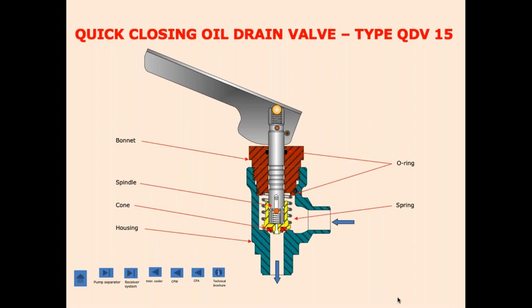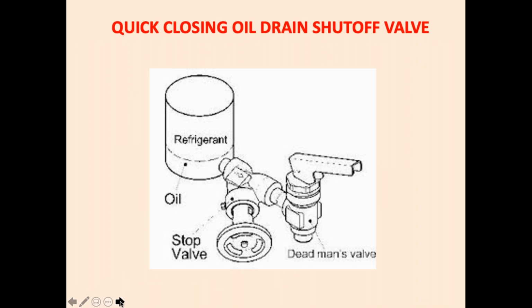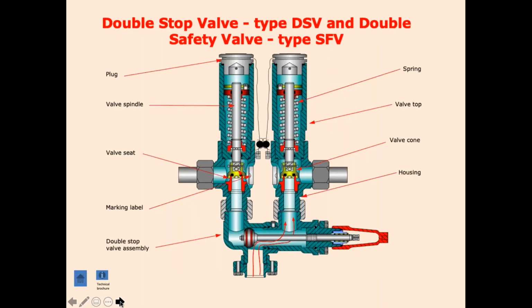It has a stop valve also behind that. The next slide, I'll show you a stop valve behind this quick closing valve. So you can keep it open or close it, and when you want to drain the oil, then only open it. This is a dual safety valve, very, very important dual safety valve for all the pressure vessels: ammonia receiver, LP vessel, accumulator, interstage cooler, etc., oil pot. Some vessels require dual safety valve, some vessels require single safety valve. Small vessels require single safety valve, but receivers, LP vessels will require a dual safety valve.